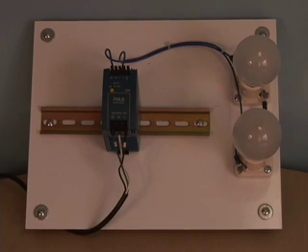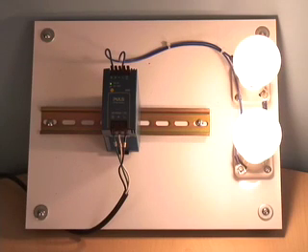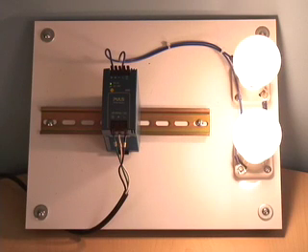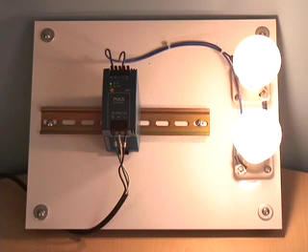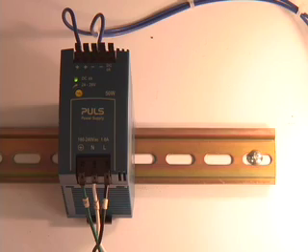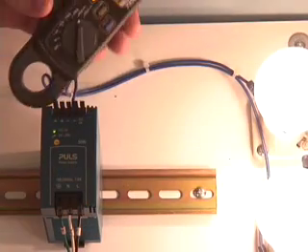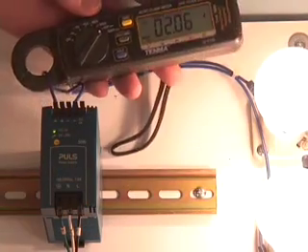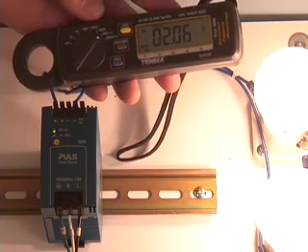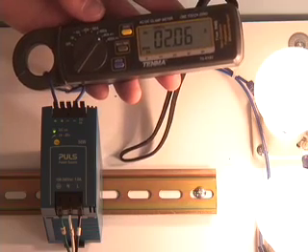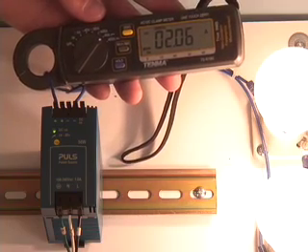When we energize the unit, the light bulbs turn on as expected. The DC OK LED on the front of the power supply indicates the power supply is functioning within the normal output voltage range. If we clamp on the ammeter, we see that the current is at or within the rated current of the supply.